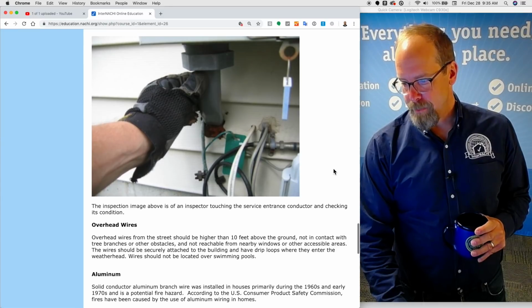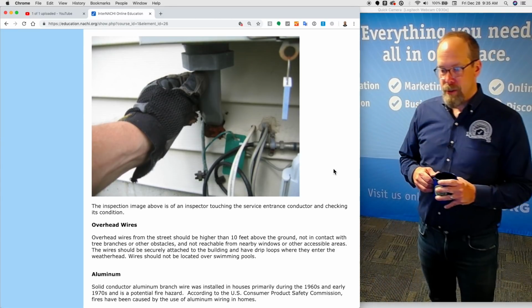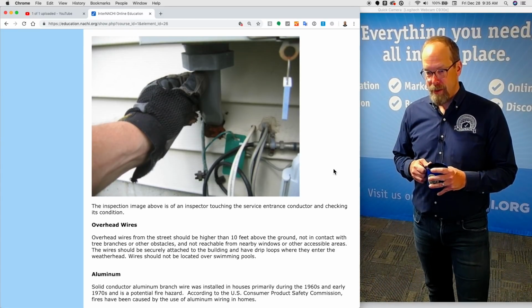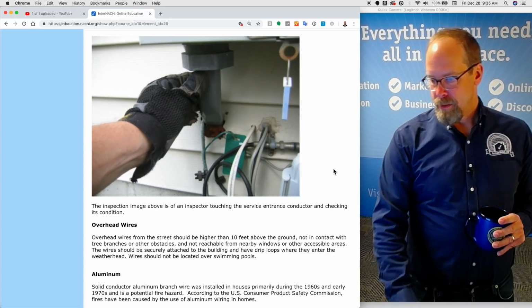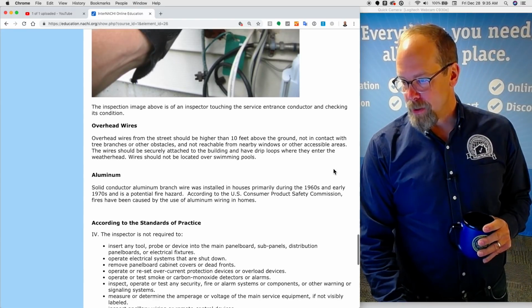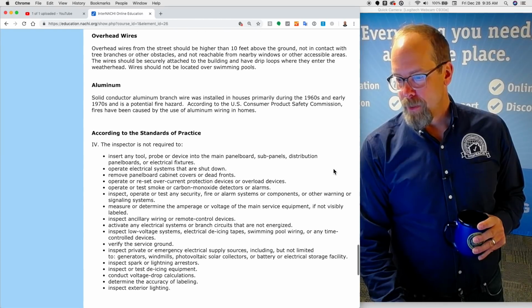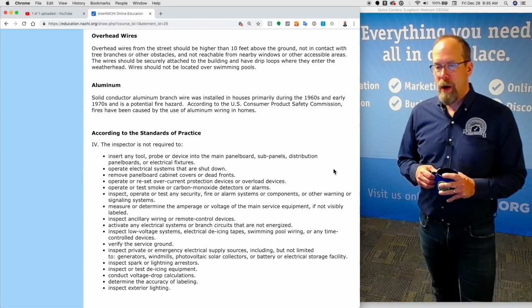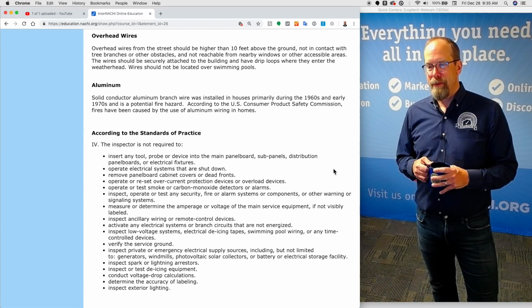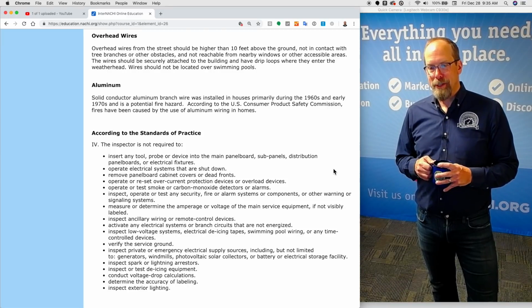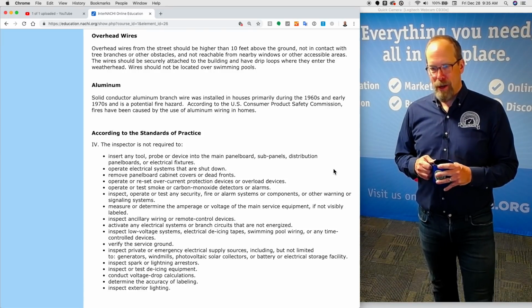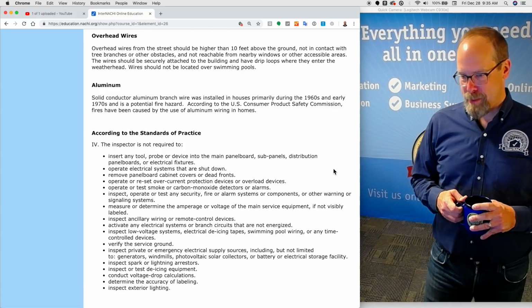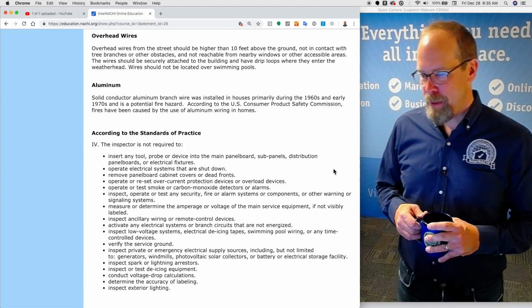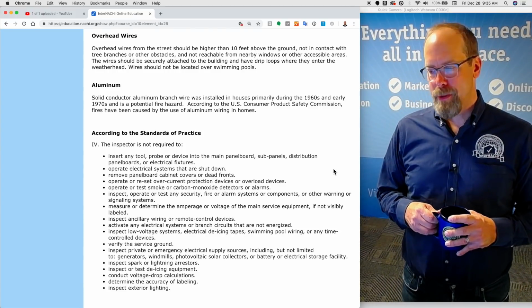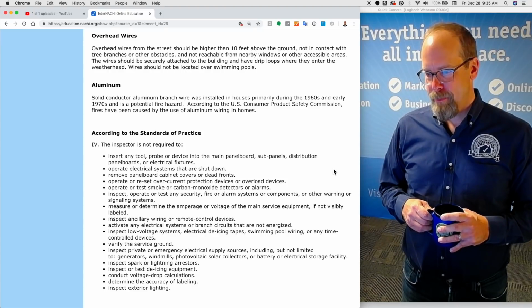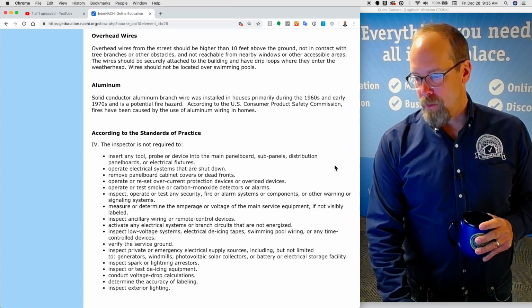Here's an inspection image above here of an inspector touching the service entrance conductor and checking its condition. You could also see the grounding wires. Overhead wires from the street should be higher than 10 feet above the ground, not in contact with tree branches or other obstacles, and not reachable from nearby windows or other accessible areas. The wires should be securely attached to the building and have drip loops where they enter the weatherhead. Wires should not be located over swimming pools.